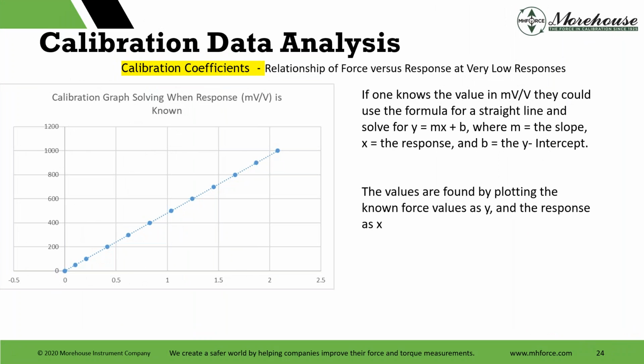If one knows the calibration coefficients, the relationship of force versus response at very low responses, if one knows the value in millivolt per volt, they could use the formula for a straight line and then solve for, that's what we were doing in the last equation, solve for mx, y equals mx plus b, where m is the slope, x is the response, and b the y-intercept. The values are found by plotting the known force values as y and the response as x.